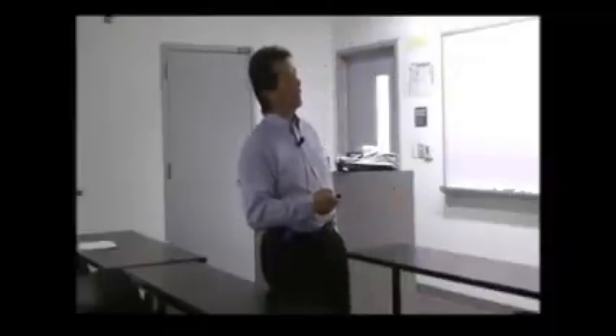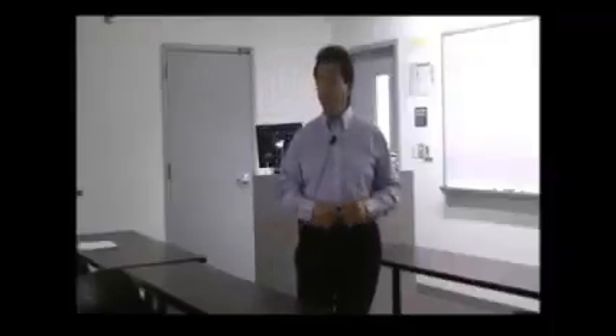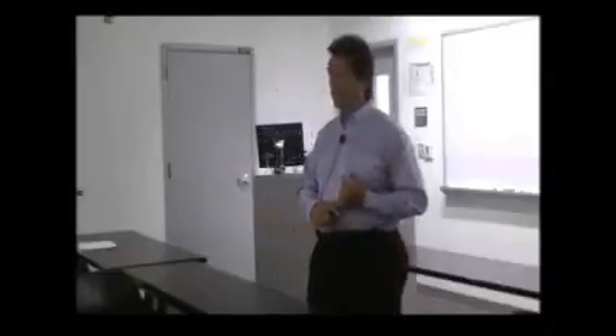Okay, I may have an exhaust fan within the room, so if I overpressurize, maybe it's a weekend and nobody's here, I'm going to use an exhaust fan to bring down the pressure in this particular room in some cases, right? Return air. But if you consider every one of these components in this little diagram, it's going to require maintenance. Regular inspections, right, on how well the systems are operating and functioning, okay? So you may get some questions on a typical air handling system, such as, what does a cooling coil do? Okay, what's an exhaust fan required for? Okay.